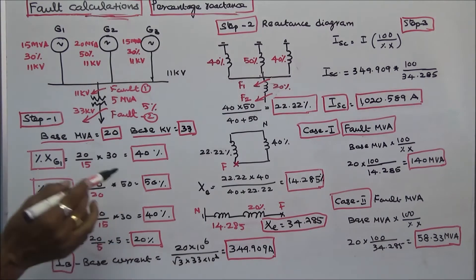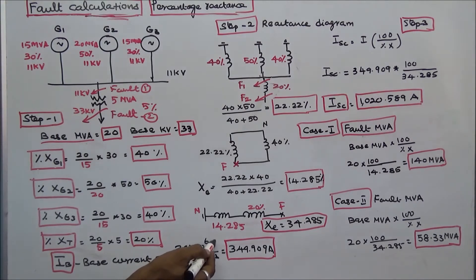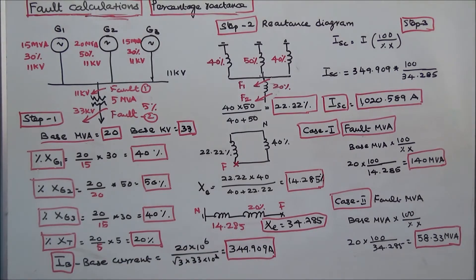Next, I calculate the base current. Base current is equal to base MVA — 20 × 10⁶ — divided by root 3 × 33 × 10³, which equals 349.909 amps.